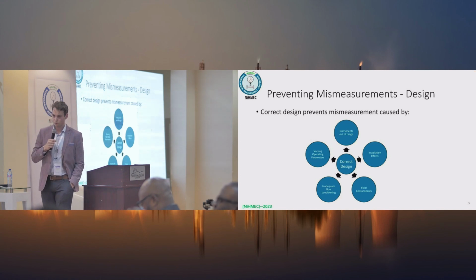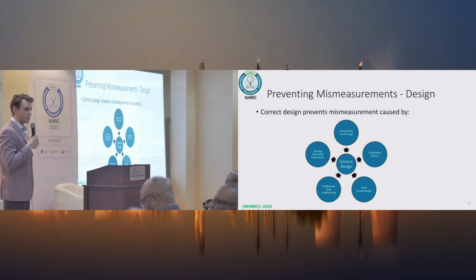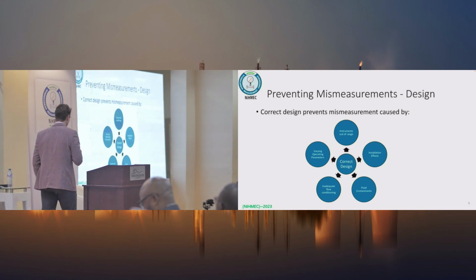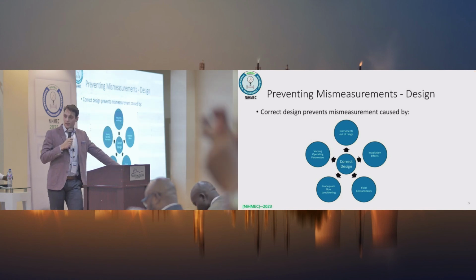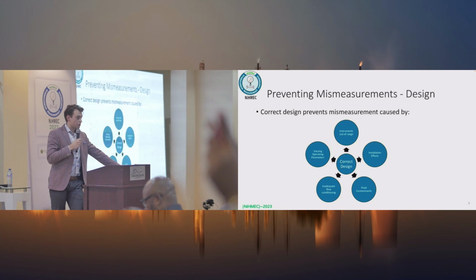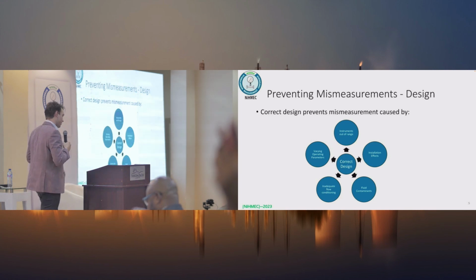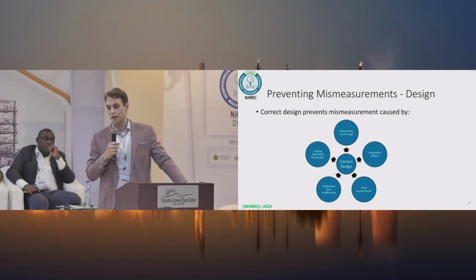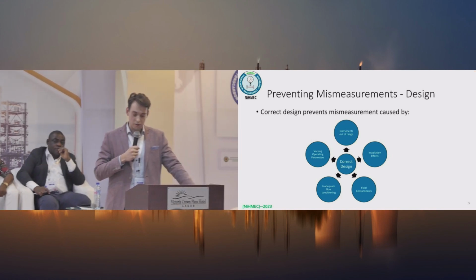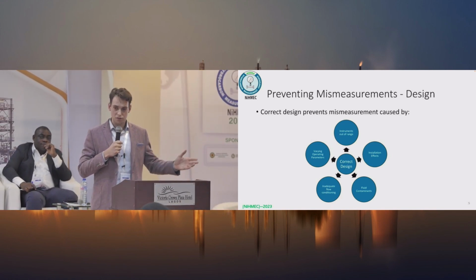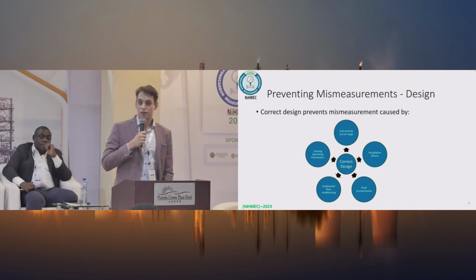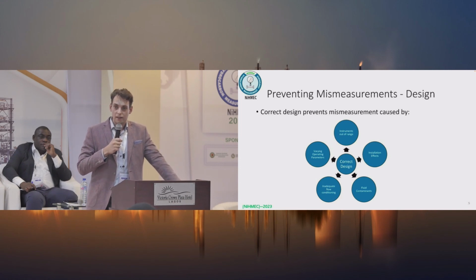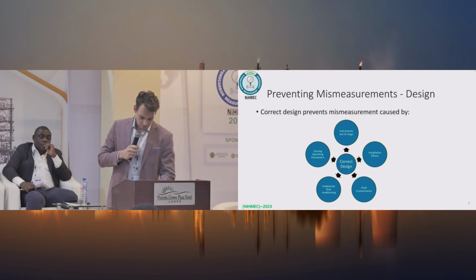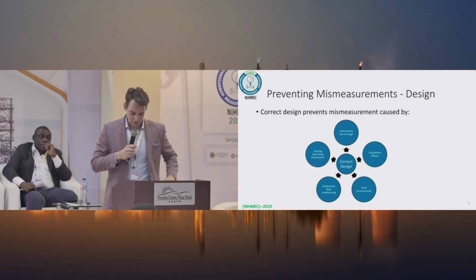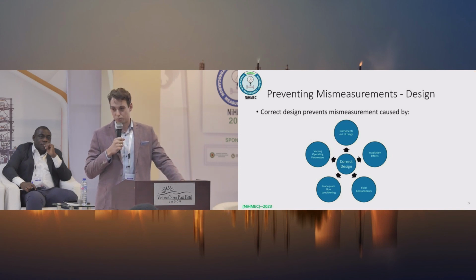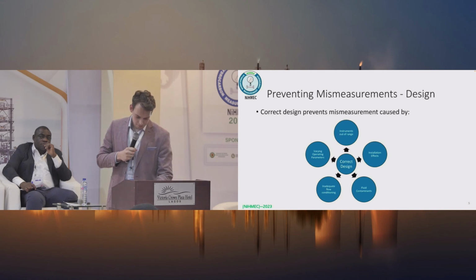There are a few factors we can rule out as potential causes of mismeasurement through correct system design. If we design correctly, instruments operating out of range should not cause mismeasurement, nor should operating parameters shifting outside of range. Inadequate flow conditioning, such as insufficient upstream sections or swirl in the system, should also not be a cause, along with fluid contaminants and installation effects. For example, a Coriolis meter installed under stress won't operate correctly, that's an example of an installation effect. Next slide, please.